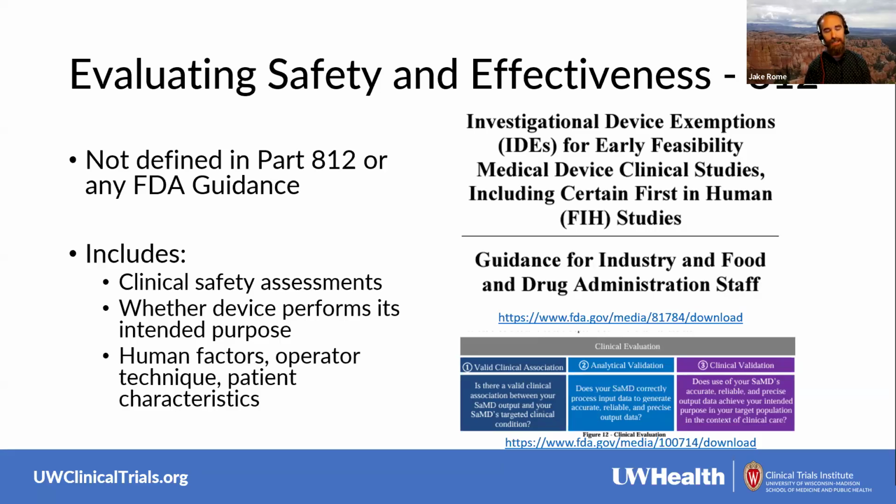And I just want to highlight it is very, very broad. If any of the aims of your study are related to safety or effectiveness of the device, looking at how it works, how it might be able to influence clinical care in X, Y, or Z way, then more likely than not, device regulations are going to apply. Now, that doesn't mean that all studies that involve a device, like a study that involves an MRI machine, are going to be FDA regulated and under 812. If you're only using a device as a tool and you're not evaluating it for any reason, then you would typically fall outside the scope of 812 as a non-clinical investigation.